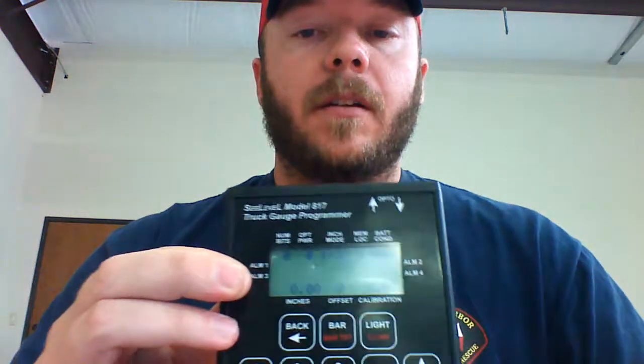On the sides here, you'll see alarm 1, 2, 3, and 4. These are the alarm settings that you can program into. They'll display out in this blank area in the middle here. Alarm 1's always going to be your high-level alarm. Alarm 2 is your audible horn. Alarm 3 is your rearm for alarm 1 and alarm 2.